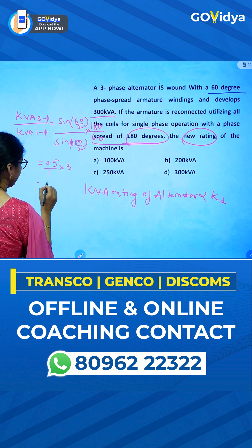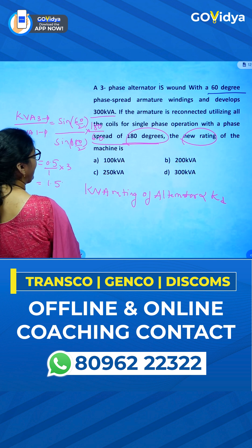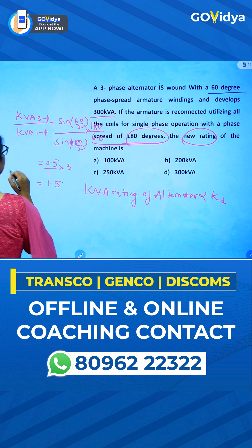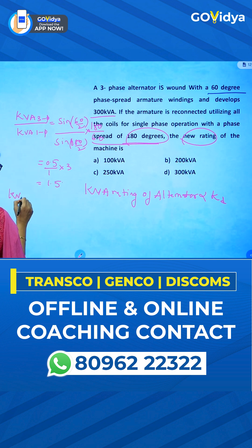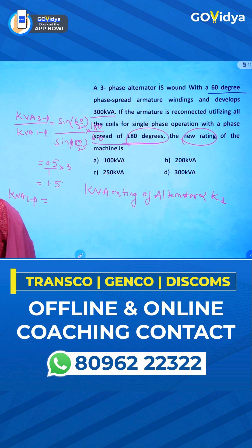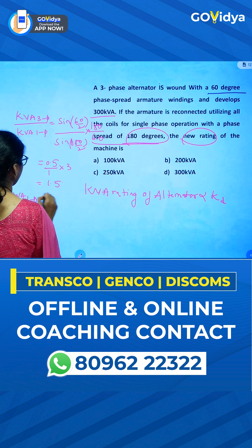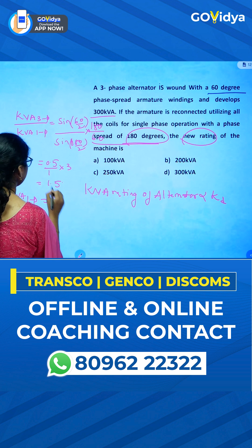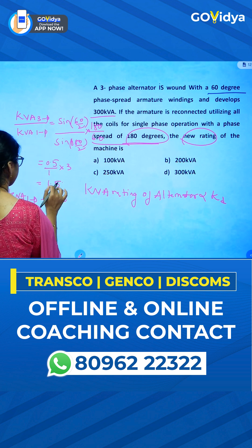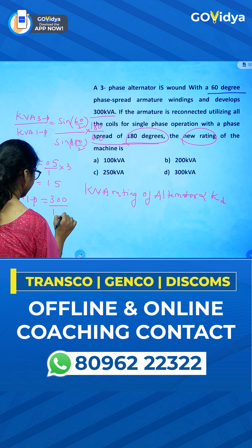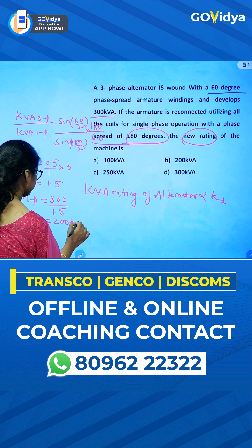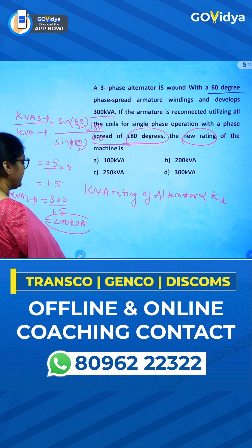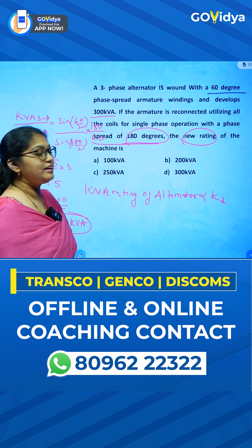This gives us 1.5. Now solving for kVA single-phase: kVA single-phase equals 300 divided by 1.5, which equals 200 kVA. So the new kVA rating will be 200 kVA.